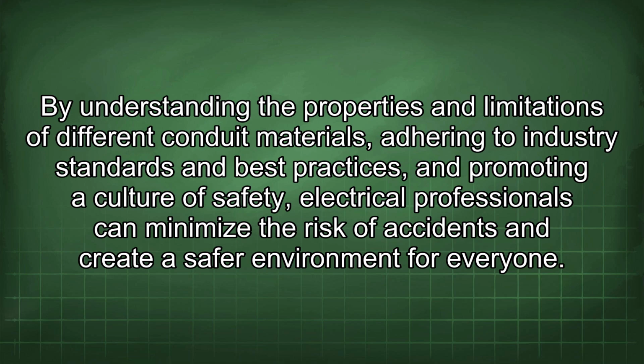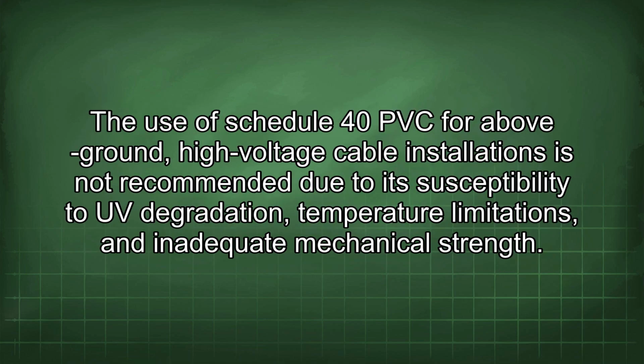The use of Schedule 40 PVC for above-ground, high-voltage cable installations is not recommended due to its susceptibility to UV degradation, temperature limitations, and inadequate mechanical strength.